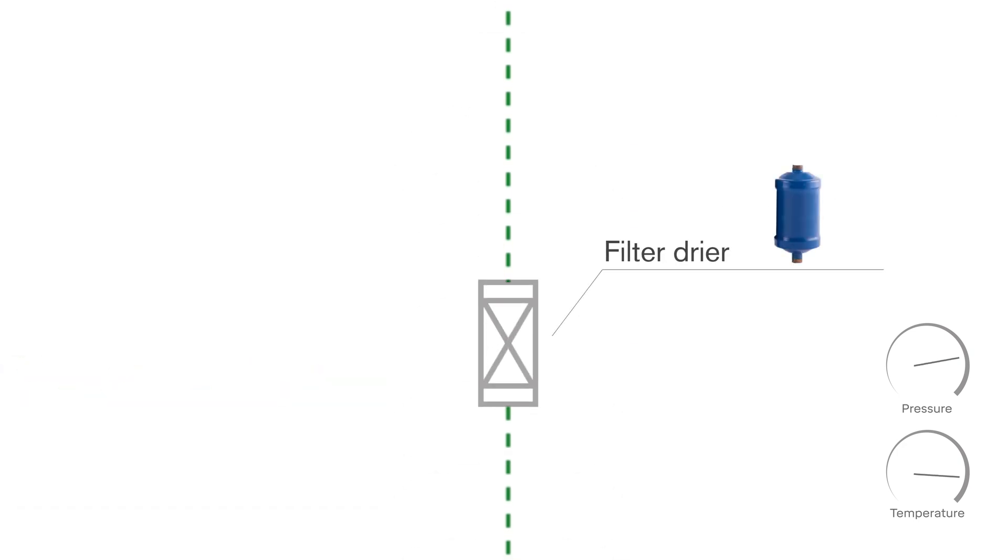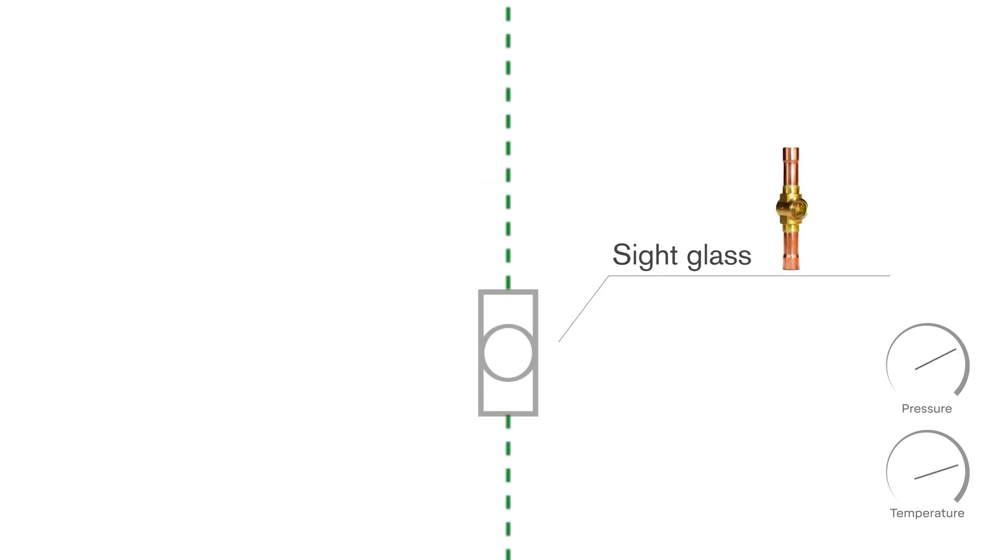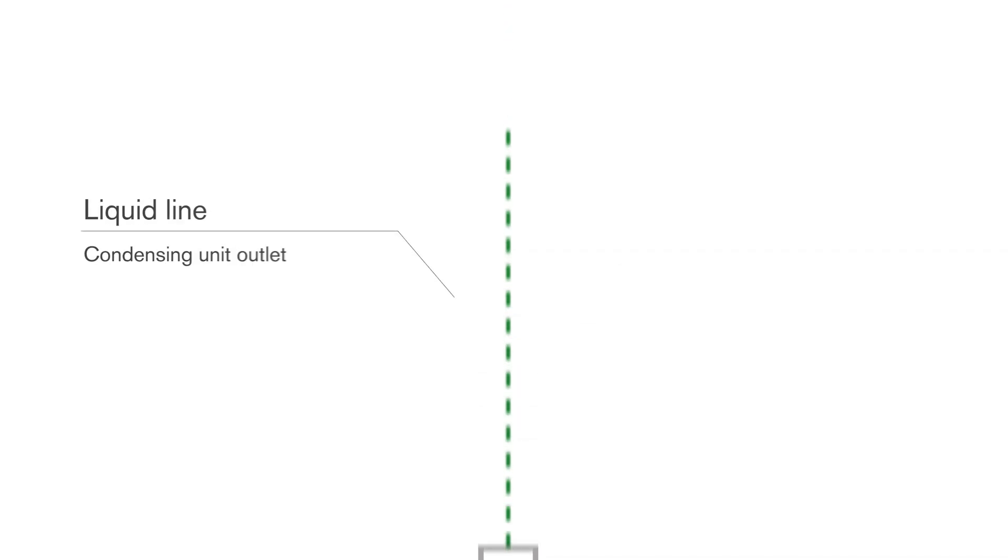Filter dryer absorbs moisture and removes solid contaminants from the refrigerant, and the sight glass with moisture indicator allows observation of the presence and flow condition of the refrigerant, which finally flows out from the condensing unit through the liquid outlet valve.